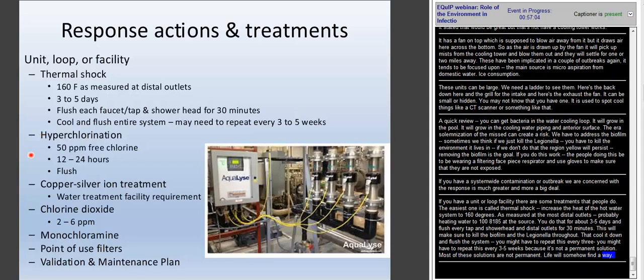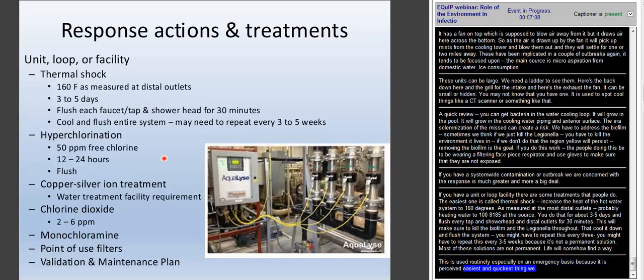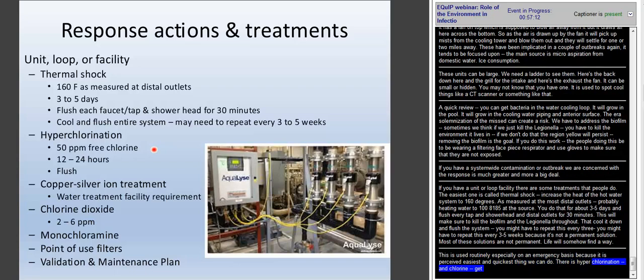There's also hyperchlorination, where you add chlorine to get a total circulating amount of 50 parts per million free chlorine throughout the entire system, as measured at the distal outlets. You want to do this for a 12 to 24-hour period, and then flush it through.